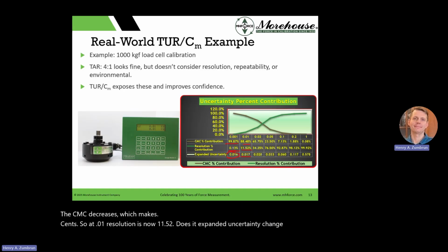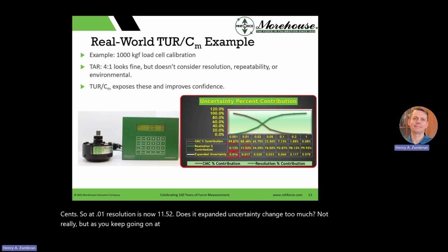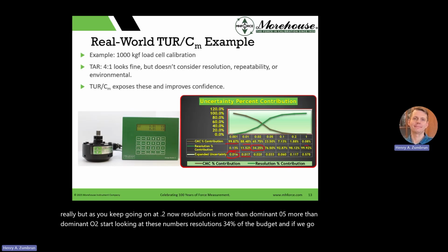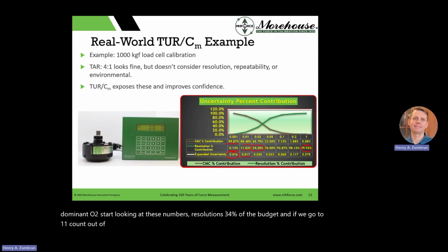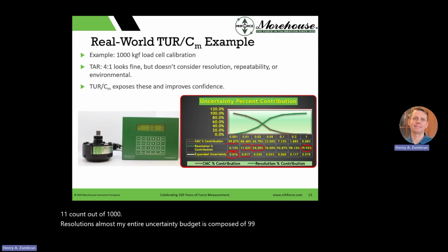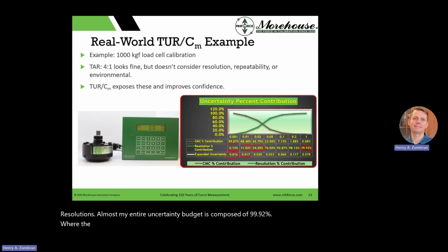Not really. But as you keep going, at 0.2, now resolution is more than dominant. At 0.05, more than dominant. At 0.2, start looking at these numbers. Resolution is 34% of the budget. And if we go to one count out of 1,000, resolution is almost my entire uncertainty budget, composed of 99.92%, where the calibration and measurement capability is only 0.08. So when we look at the contributors to uncertainty and the weight of each contributor, basically that resolution, as it gets coarser, becomes more dominant. Hopefully that makes sense.